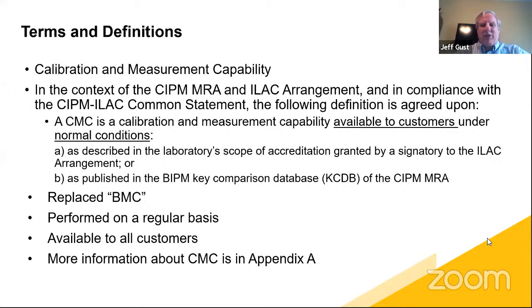So it says, what is your uncertainty in a fairly routine measurement process? We're saying, yes, you might get a much better uncertainty if you spent 6 months measuring this device and averaging 1 million measurements, but that's not a routine measurement. These CMCs are to talk about a routine measurement. If you send a meter to a lab, what do you generally get for that meter calibration?